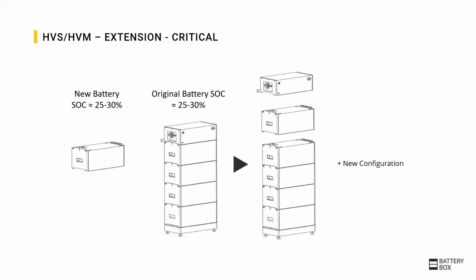If the battery should be extended later or a module is exchanged, it is very important to have a similar state of charge in all modules. As new modules arrive with about 25 to 30% SOC, the original battery should be turned off at about the same SOC. Then the new module can be simply added. After this, the configuration has to be done again with the new module quantity.